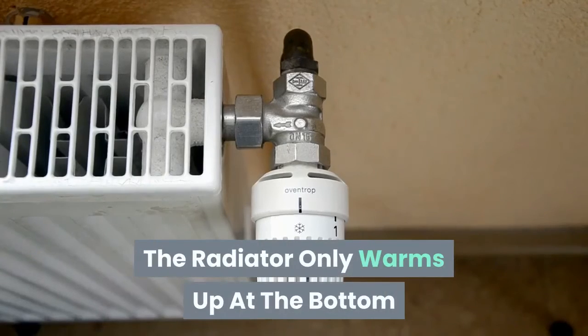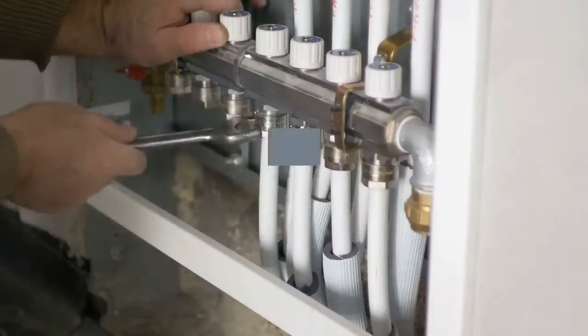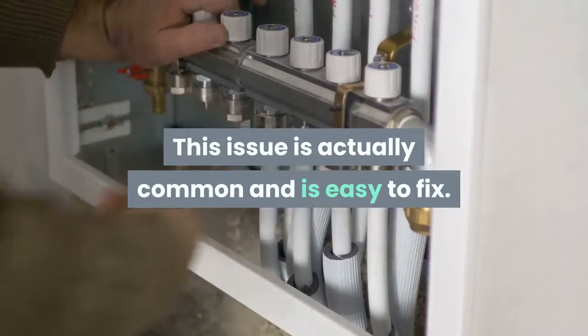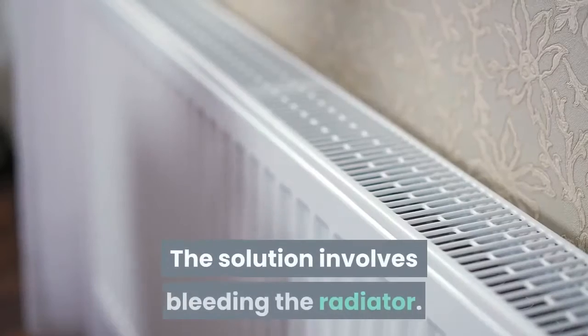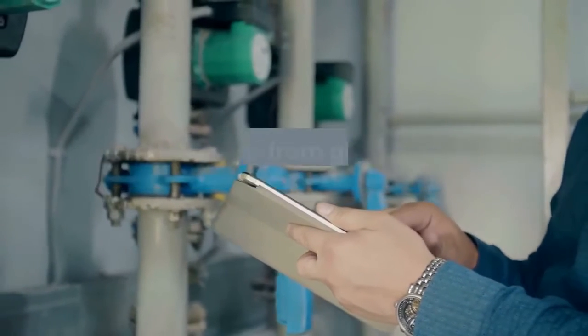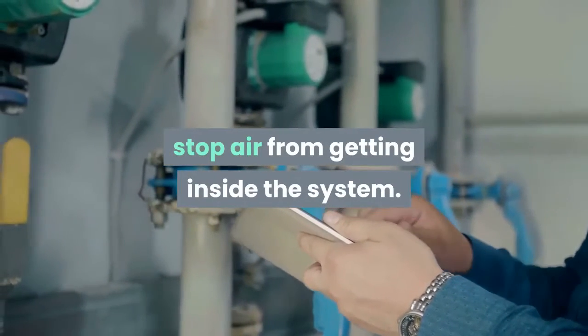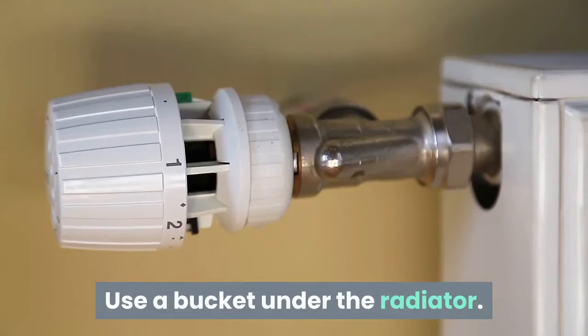The radiator only warms up at the bottom. This issue is actually common and is easy to fix. The solution involves bleeding the radiator. The pump needs to be switched off to stop air from getting inside the system. Use a bucket under the radiator.